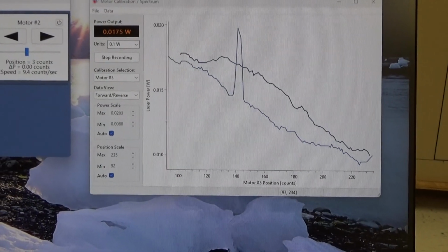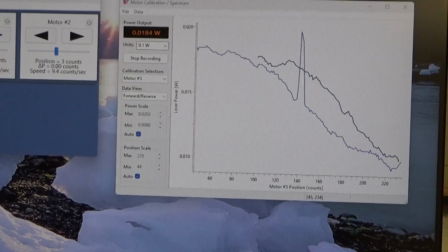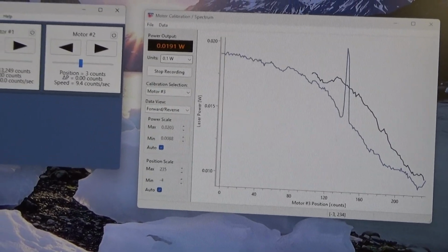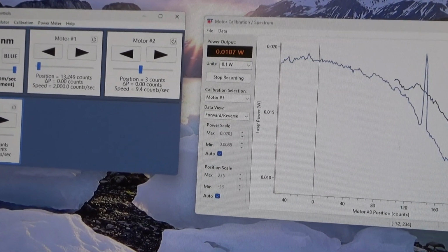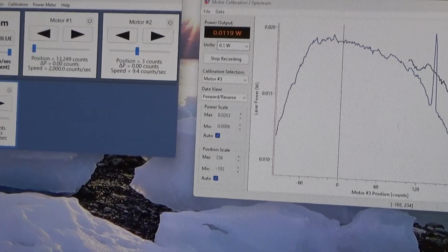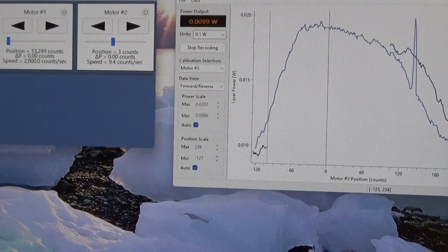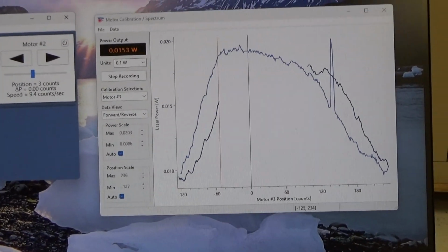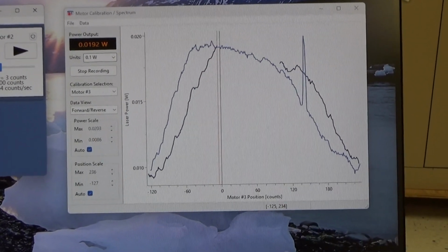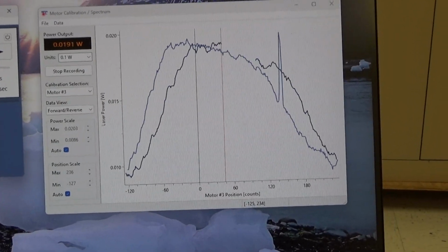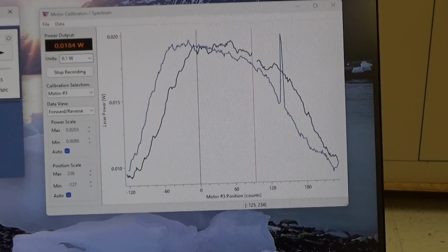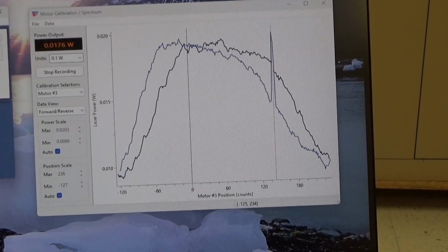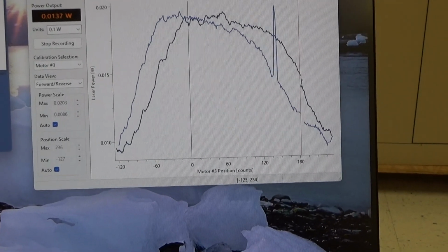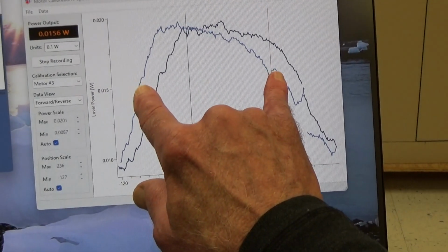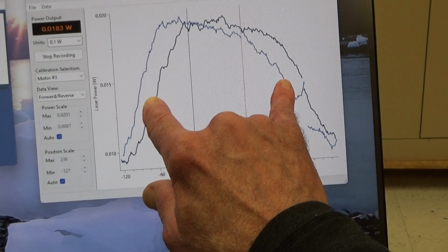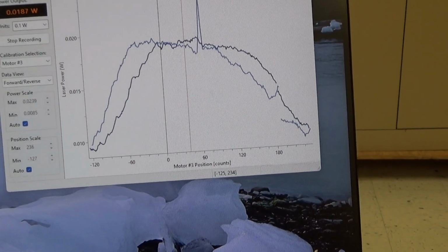Little blip from my electronics. Now you'll notice that the forward and backwards curves are offset slightly from each other. This is predominantly due to the fact that I'm using a thermal power meter, and there is a lag time in its response. So the best spot for positioning the crystals is always going to be right centered between the two descending lines on each of the curves. So right about there. Okay.